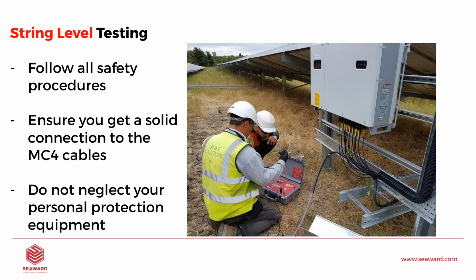Or if we open up an inverter, we just need to be careful because that inverter will hold a capacitive charge, and we just need to make sure that that charge has dissipated before we connect our instrument, or else we could get some problems there, and we could damage the instrument. We could have an arc. If you are using the probe tips, either in the combiner box in the top of the harness or inside an inverter, just be very careful not to pull the probe away during the test, because again, you're going to pull an arc, and that's going to damage hopefully just the unit and not yourself.